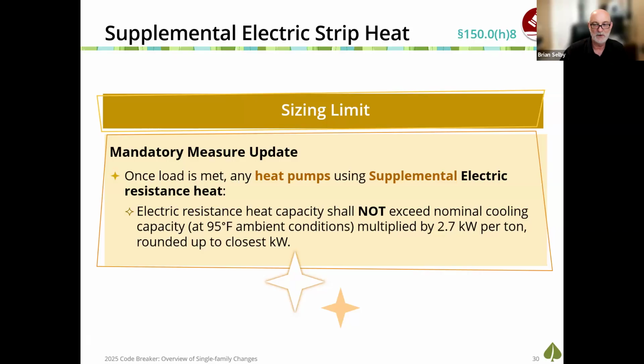Once the heating load is met, any heat pumps using supplemental electric resistance heating shall not exceed the nominal cooling capacity. So the heating capacity cannot exceed the cooling capacity, and that's multiplied by 2.7 kilowatts per nominal ton of that equipment. So there are some limitations on the amount of electric heat strips that can be built into a heat pump.